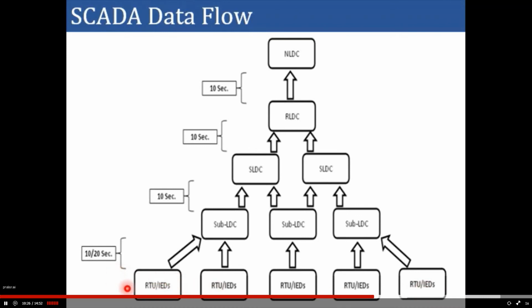These devices keep sending data to the Sub Area Local Dispatch Center, which is the first SCADA control center, where RTU data is aggregated and the local area display is seen on the HMI. This is the area monitored and controlled by the SCADA application installed in this control center.